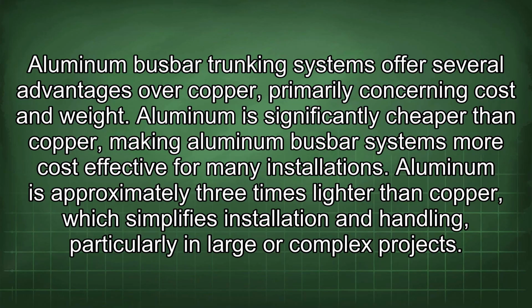Aluminum busbar trunking systems offer several advantages over copper, primarily concerning cost and weight. Aluminum is significantly cheaper than copper, making aluminum busbar systems more cost-effective for many installations. Aluminum is approximately 3 times lighter than copper, which simplifies installation and handling, particularly in large or complex projects.